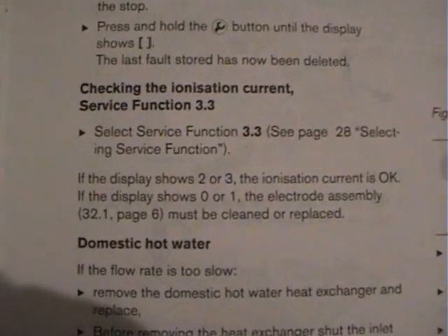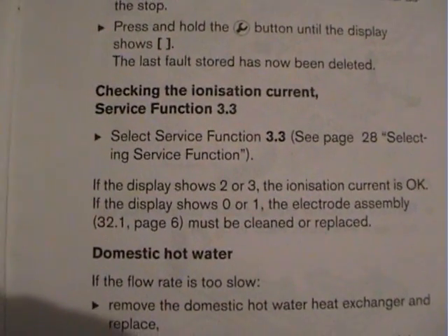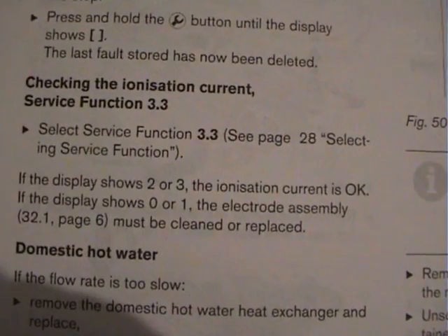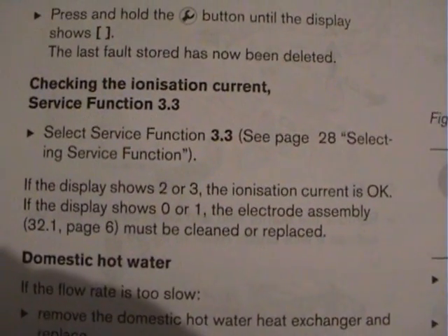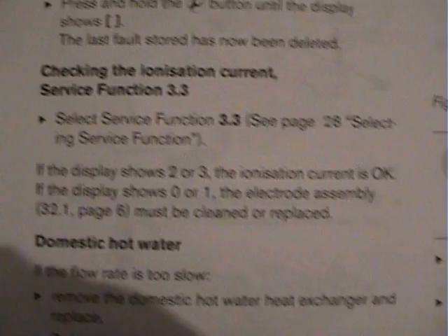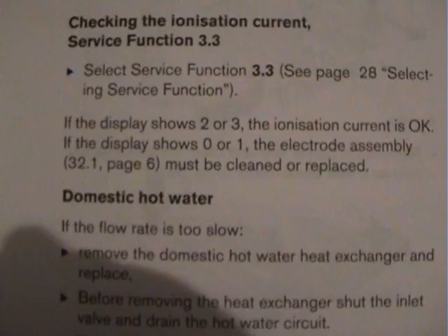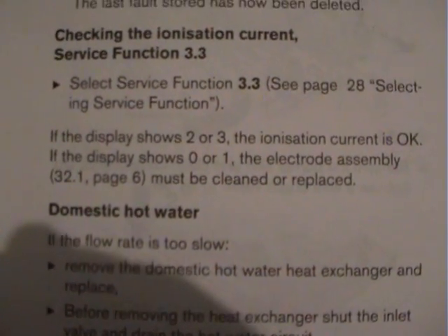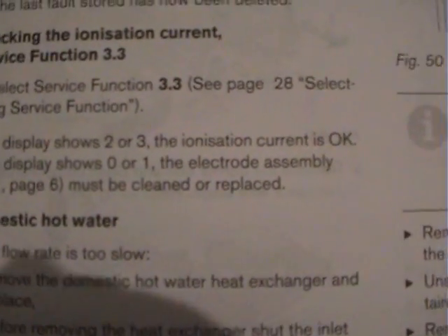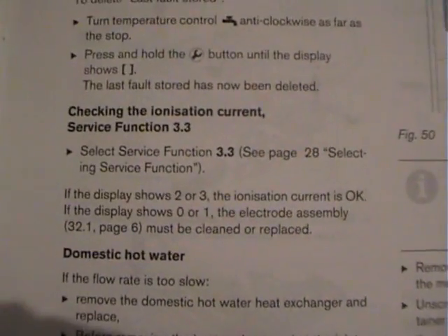One last thing — because this camera should focus on the book better. I want to do it in HD. I think you can see that. Checking the ionisation current — service function 3.3, and that's what we did. It does tell you in the book, but it's not laid out clearly at all. It does say: if the display shows 0 or 1, the electrode assembly — see? And then it says 32, figure one, page six. Must be cleaned or replaced. So the information is there, it's just not laid out in any formal manner.